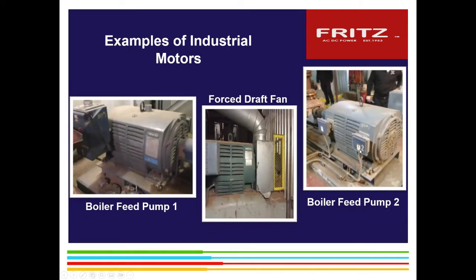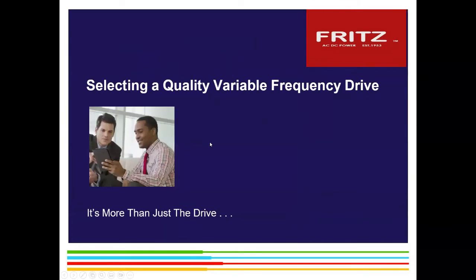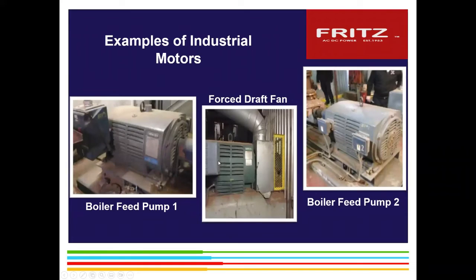So these are some examples of a power plant that I retrofitted. These happen to be 750 horsepower medium voltage motors on boiler feed pumps going into a chip-fired burning plant, and the draft fans, and these had a tremendous return on investment. We saved on average, I think they reduced their power consumption about $450,000 a year, and it's retrofitting about 40 motors in their plant.